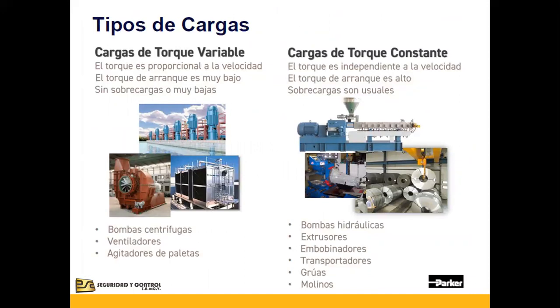Los variadores se pueden separar dependiendo del tipo de carga. Para cargas de torque variable, el torque es proporcional a la velocidad y el torque de arranque siempre va a ser muy bajo. Pueden ser usados para bombas centrífugas, ventiladores o agitadores de paleta. Para torque constante, el torque es independiente a la velocidad, el torque de arranque es alto y las sobrecargas son muy usuales. Estas aplicaciones se pueden conseguir en bombas hidráulicas, extrusores, bobinadores, transportadores, grúas y molinos.